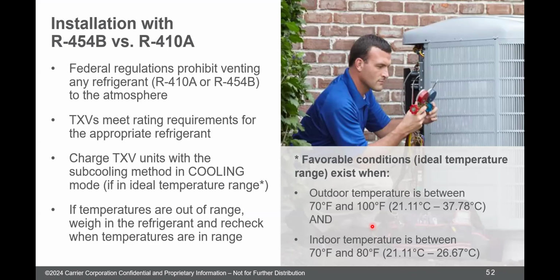And we want to do it that way normally because the inverter is kind of ramping up and down. So it's kind of hard to do it any other way and not have it keep tweaking on you. If it's a single stage unit or a two-stage unit, a non-inverter, then in those cases for R410A and R454B, we're charging via the subcooling method. That's the normal way to do that. So it's the exact same method.